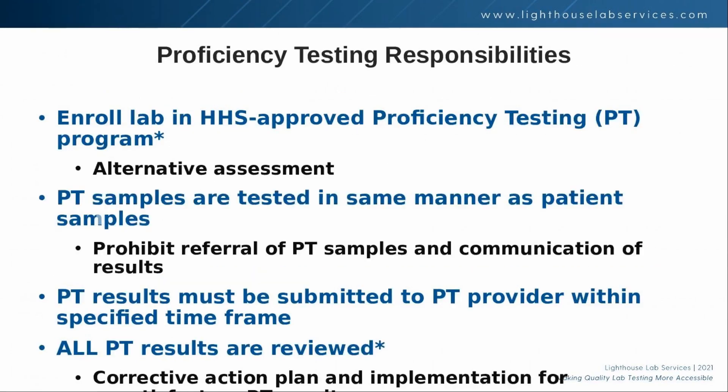As previously mentioned, proficiency testing is one of the ways to ensure accuracy of results produced by the laboratory and is a requirement for CLIA and accreditation agencies. The lab director is responsible for enrolling the laboratory in an HHS-approved PT program that is appropriate for the lab's test menu. For any analytes that may not be covered by commercially available PT programs, alternative assessment is often required.